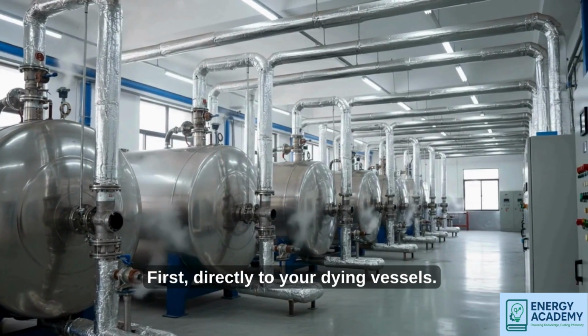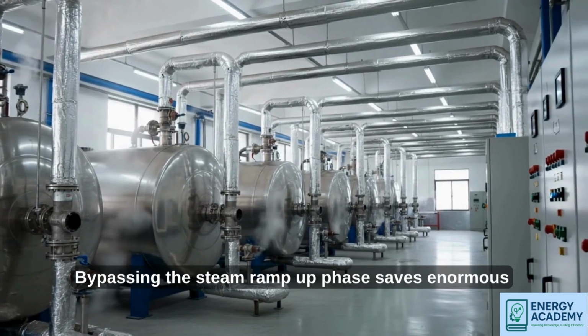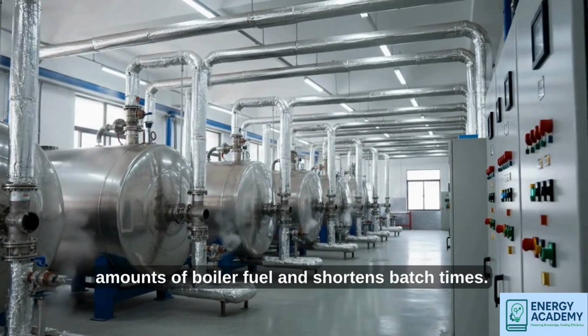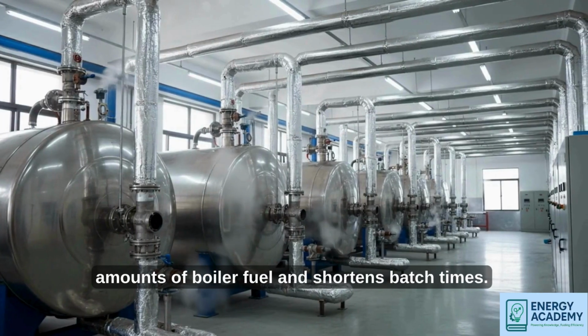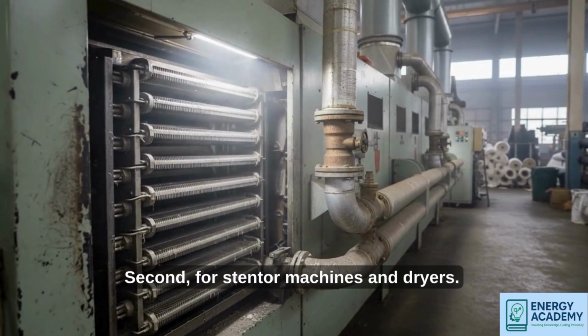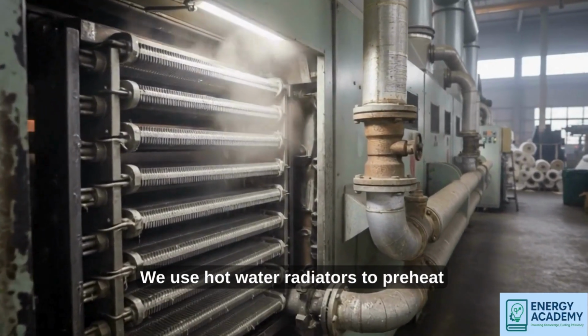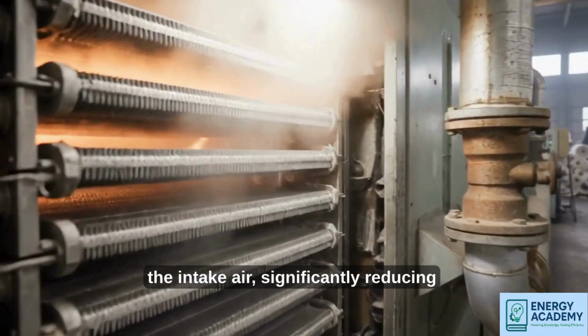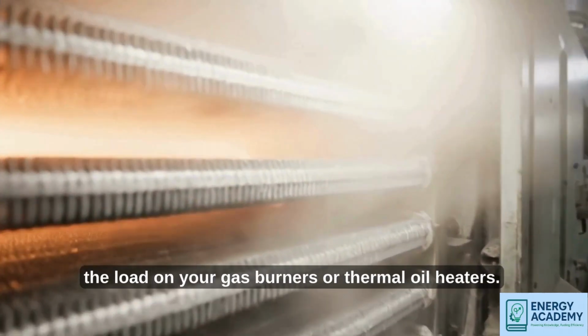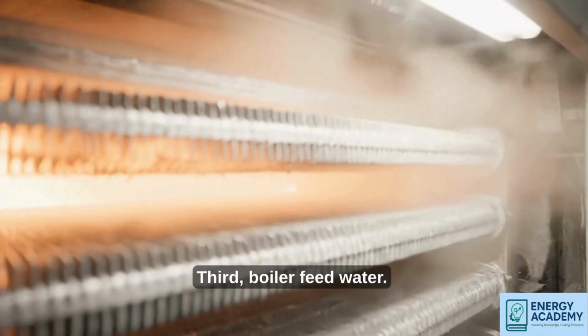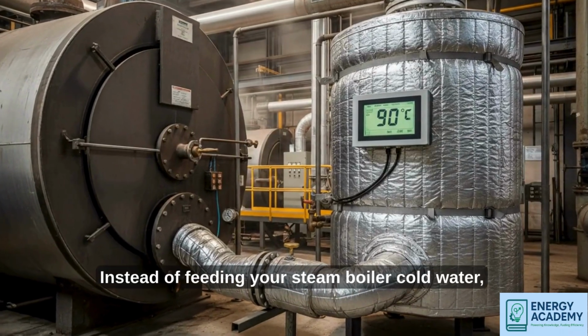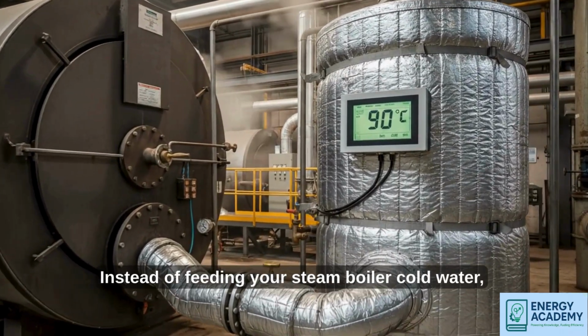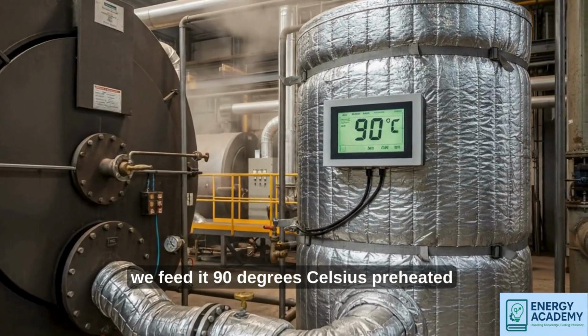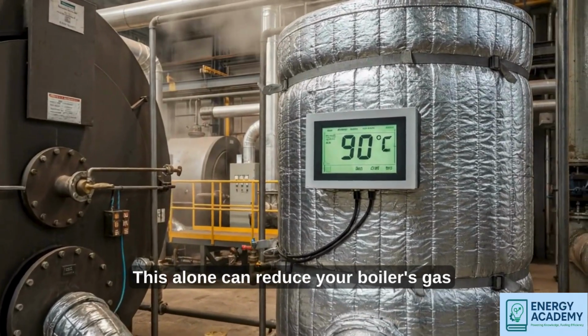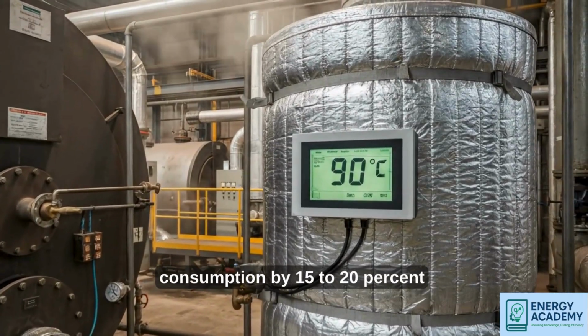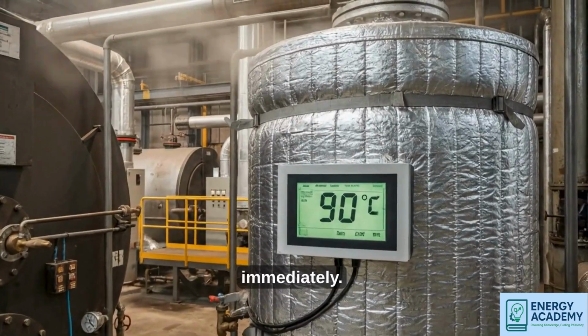First, directly to your dyeing vessels. Bypassing the steam ramp-up phase saves enormous amounts of boiler fuel and shortens batch times. Second, for stenter machines and dryers. We use hot water radiators to preheat the intake air, significantly reducing the load on your gas burners or thermal oil heaters. Third, boiler feed water. Instead of feeding your steam boiler cold water, we feed it 90 degrees Celsius preheated water. This alone can reduce your boiler's gas consumption by 15 to 20% immediately.